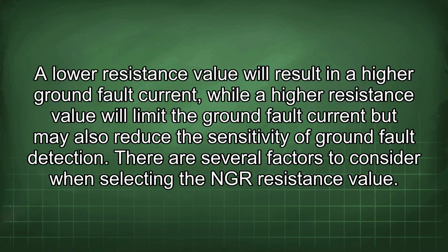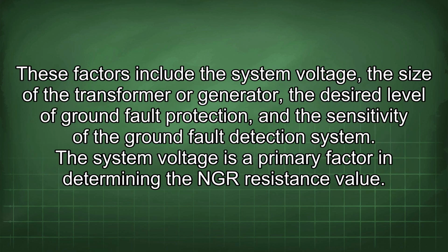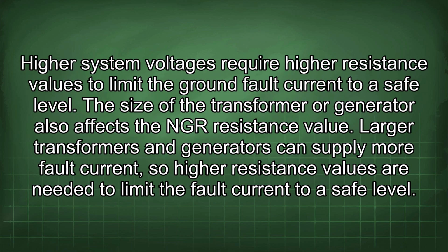There are several factors to consider when selecting the NGR resistance value. These factors include the system voltage, the size of the transformer or generator, the desired level of ground fault protection, and the sensitivity of the ground fault detection system. The system voltage is a primary factor in determining the NGR resistance value. Higher system voltages require higher resistance values to limit the ground fault current to a safe level. The size of the transformer or generator also affects the NGR resistance value. Larger transformers and generators can supply more fault current, so higher resistance values are needed to limit the fault current to a safe level.